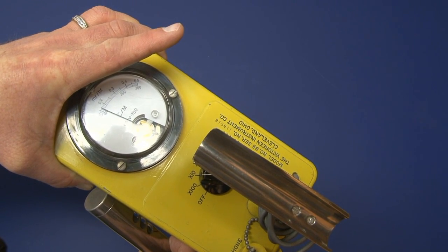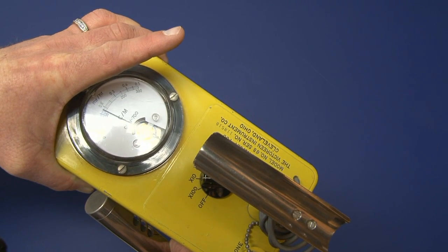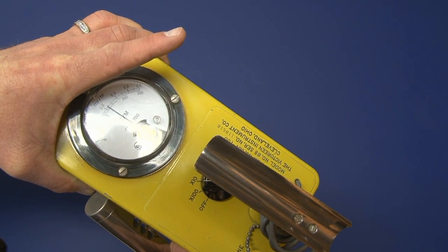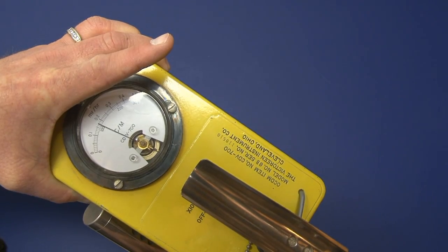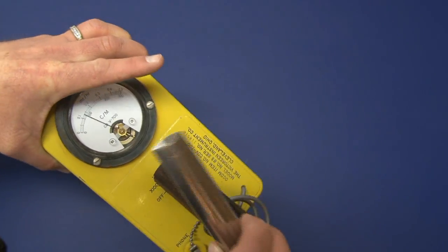The instrument response time is about 8 seconds, so give it time to respond. But you can see this one's reading in that 2 mR per hour range, so this would be okay and we could proceed to use the instrument since it checked out okay.